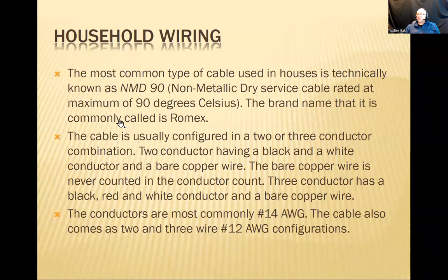All right. So household wiring, it's the most common, and I'm going to read some of that. The most common type of cable used in houses is technically known as the NMD90, and the NMD90 stands for non-metallic dry service cable. What's a service cable? It's a cable that provides power. What could we have other than service cable? Well, we could have signal cable, like for the microphones and so on, speaker cable, whatever. But service cable is a cable that provides power. So NMD90 stands for non-metallic, dry.